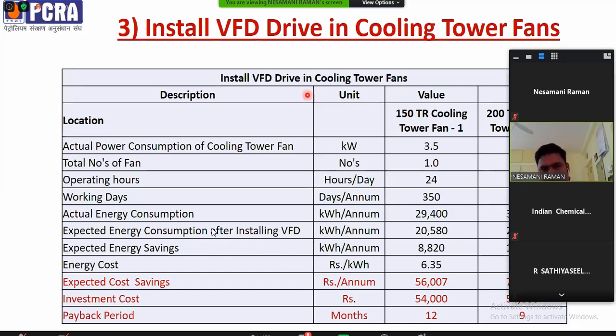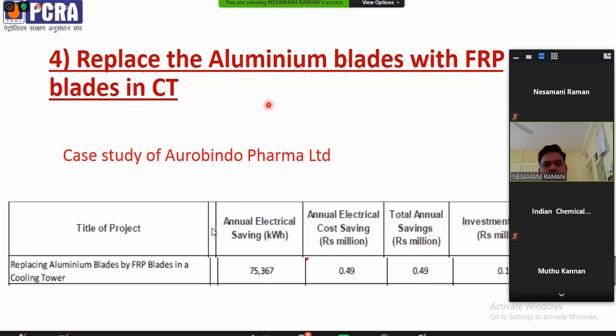So we suggested installing a VFD drive on the cooling tower fans. It will operate the fans as per the temperature. We took an offer from one of the vendors, and the cost was almost 54,000 per drive, including temperature sensors and everything. When we calculated the energy saving, the payback was less than 1 year. So this is one of the good solutions for energy conservation in chemical industries, particularly in cooling towers. And the fourth option is replacing the aluminum blades with FRP blades in cooling towers.